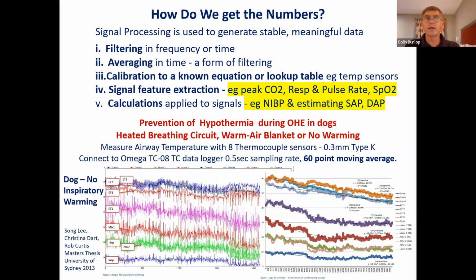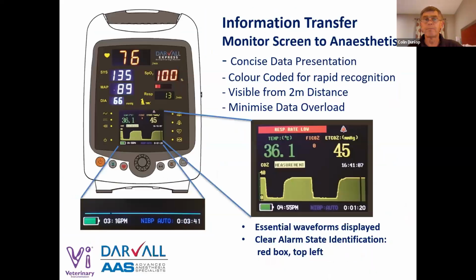So we certainly have signal modifications made on capnography, respiratory and pulse rate and SpO2 inputs. And we have calculations applied to those signals for particularly things like NIBP, where oscillometric systems deliver systolic and diastolic numbers, but they actually only measure the mean. So the mean number is real and the rest are made up by whatever software and algorithm is put into that machine by the manufacturer.